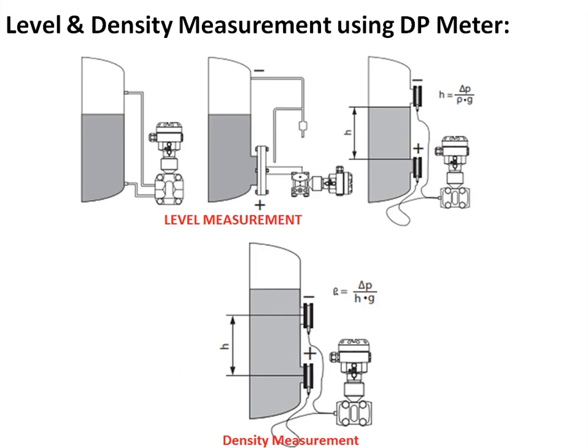When a constant head (height H) is maintained in the tank, the measured differential pressure is directly proportional to the density, given by density = delta P / (H × G). H is constant because we are maintaining a constant head in the tank, and G is constant as the acceleration due to gravity.